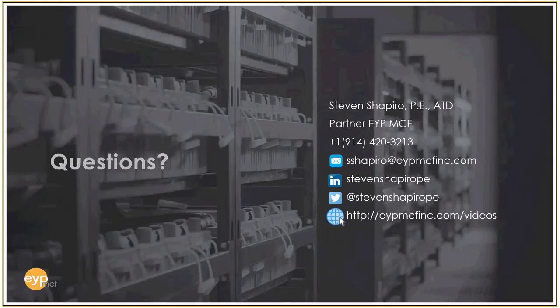One of the things that we are looking at relative to lithium-ion batteries and their application in a facility is putting them in a dedicated 3-hour fire rated room to minimize their impact on the overall scheme of the facility. We do the same thing when we're looking at large size fuel oil tanks inside the building. When we try to put day tanks in over a certain capacity, code says that they can't be in the building. Well, one of the ways to deal with that code item is to put it in a 3-hour rated room, and effectively it's a separate building within a building. And that's one of the ways that we can deal with a lithium-ion battery environment.